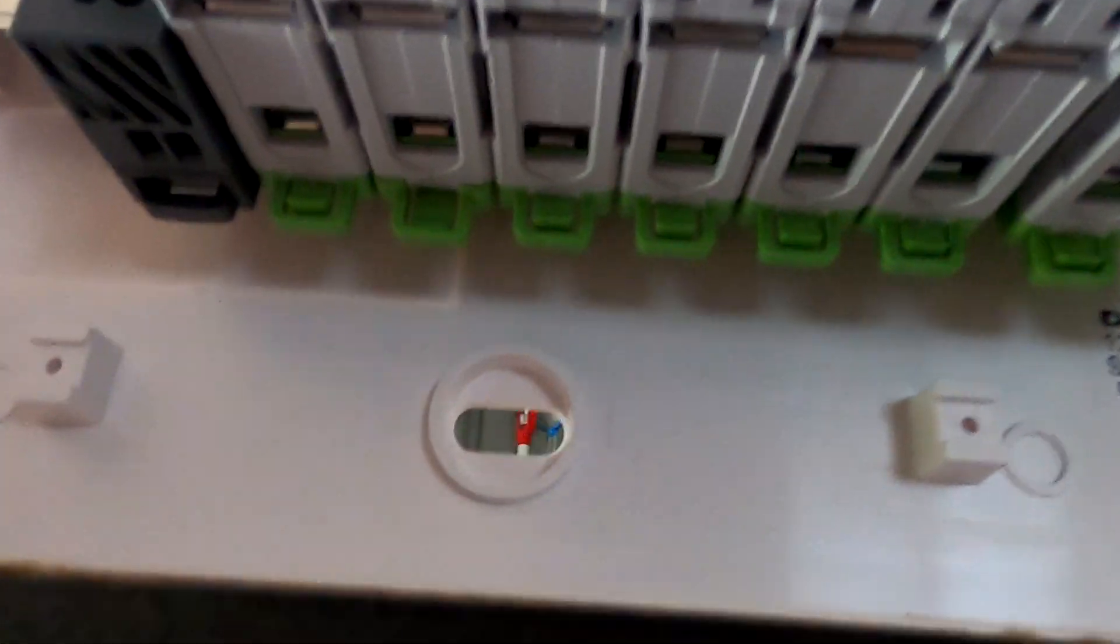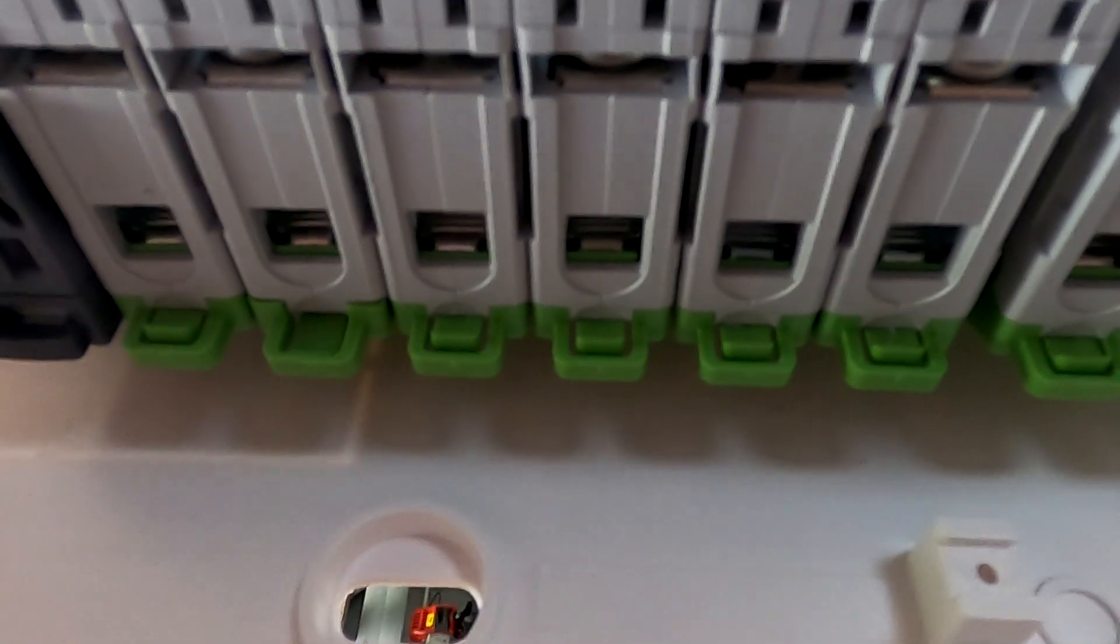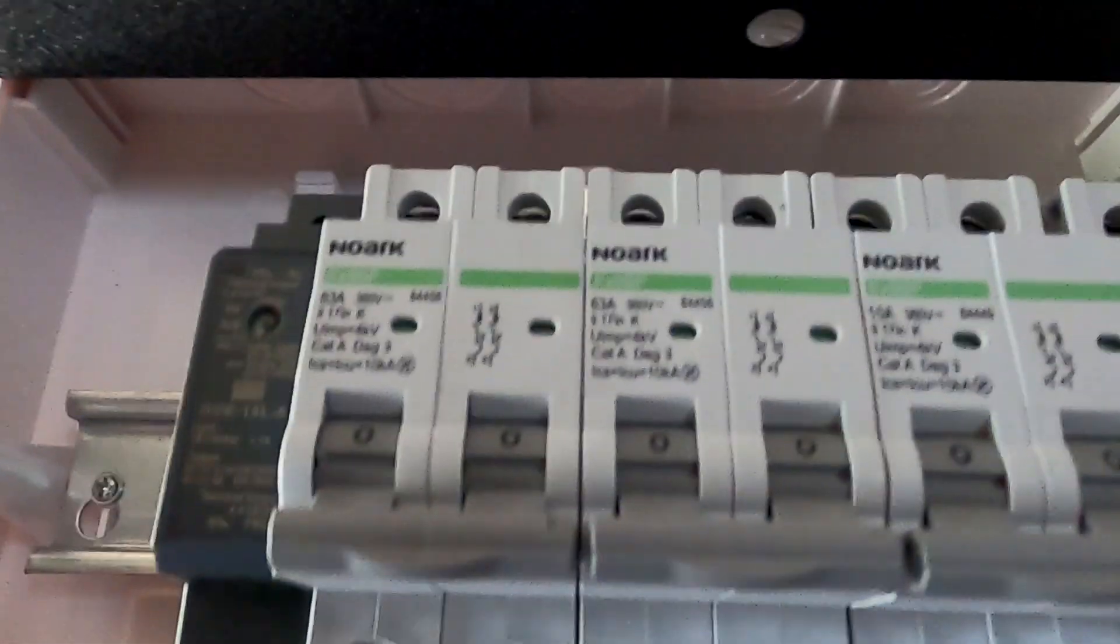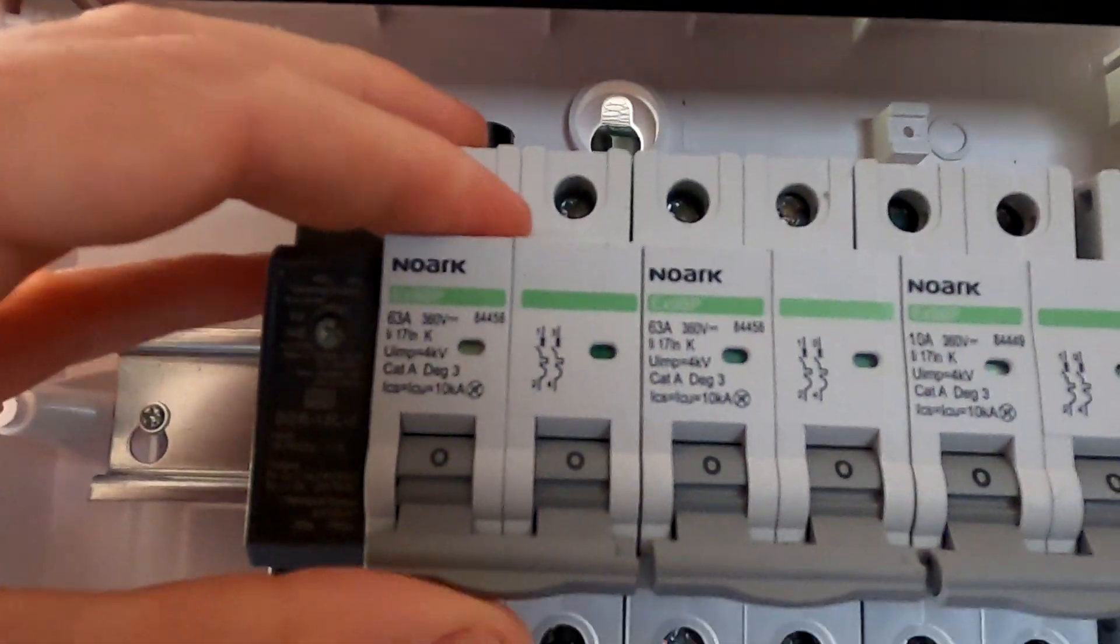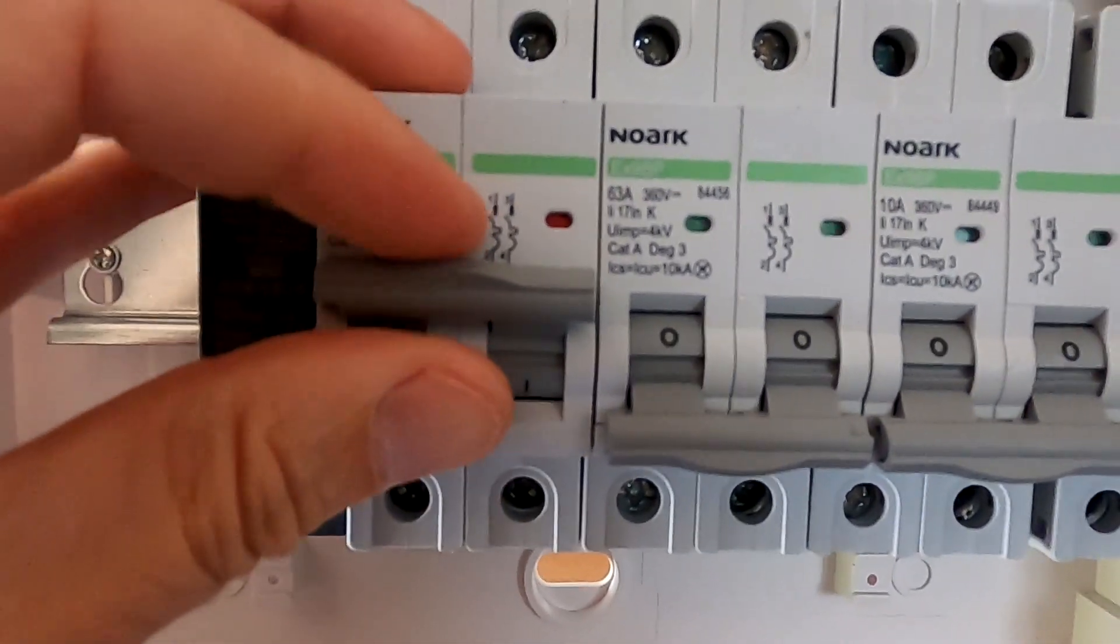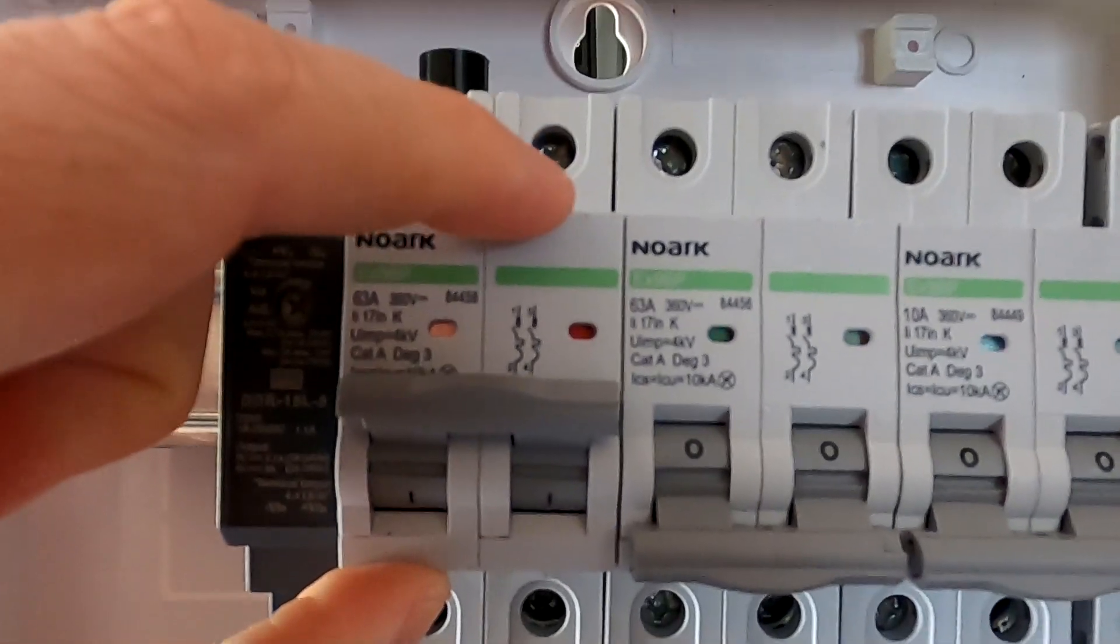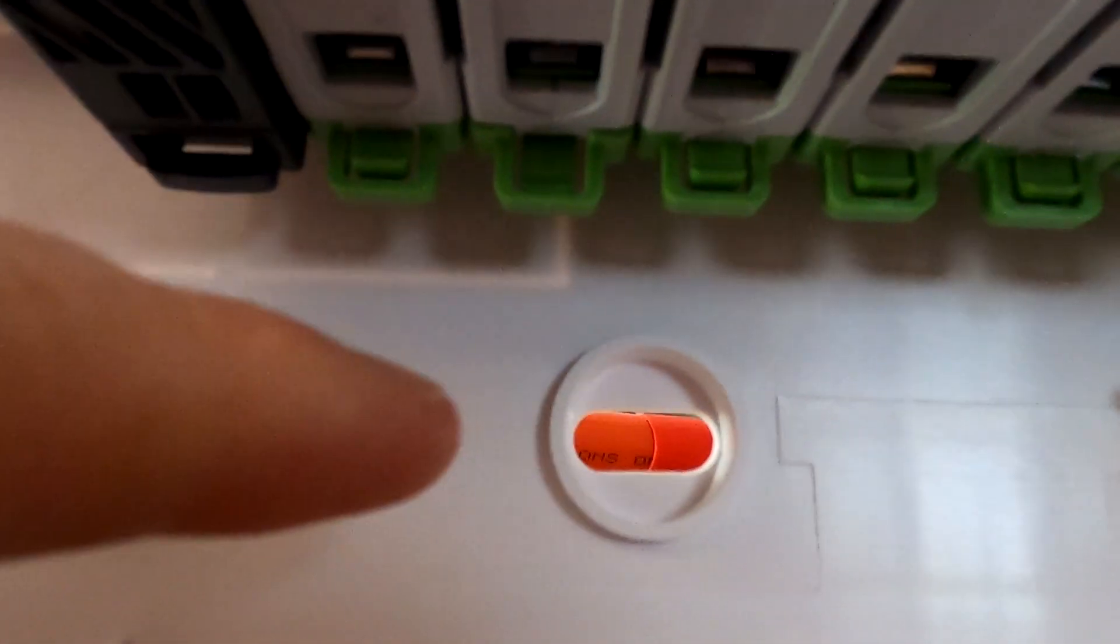While this is a funny idea, it is not possible because we have an isolating circuit breaker. We've got positive and negative next to each other. We cannot just connect all these pins together here, this would not work anymore as an isolator. There are solutions out there with these staggered bus bars you just insert into these circuit breakers and they have their pins in an offset, so they are only connecting every second circuit breaker then to this bus bar. I have not seen them for these breakers though, because all these terminals are in one row.